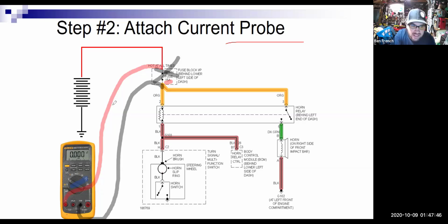The downside of doing this is that my meter is vulnerable to getting the fuse blown out of it, and I could possibly damage the meter if there was a big short in the circuit. However, if there was a big short, the fuse hopefully would blow. So there's a little risk, but you could put your meter in series, take the fuse out, put it in series with the circuit just like I've drawn, and then try to turn on the horn and see what happens.